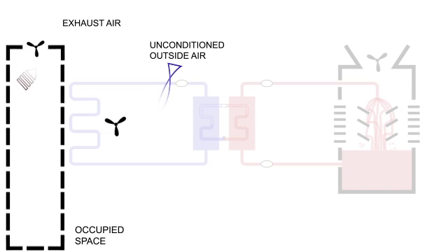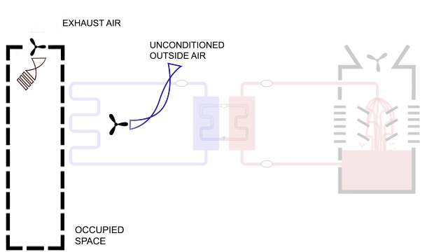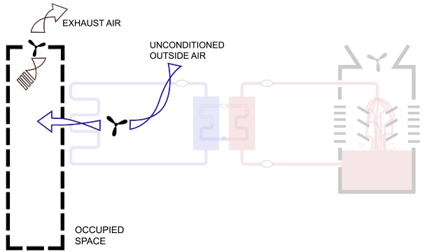When an economizer mode, often called free cooling, is deployed, technicians must be mindful that it isn't too cold. Coils in the air handling unit may freeze and bust, or ice may form in the cooling tower, busting that equipment.